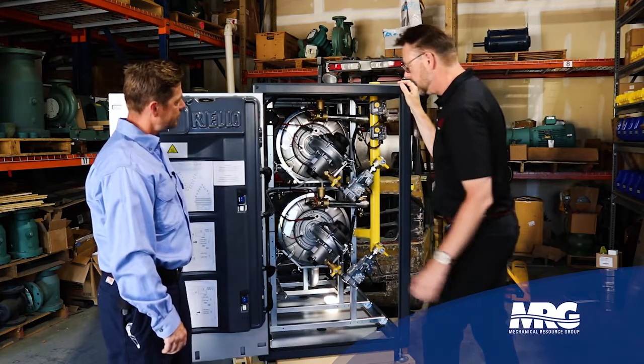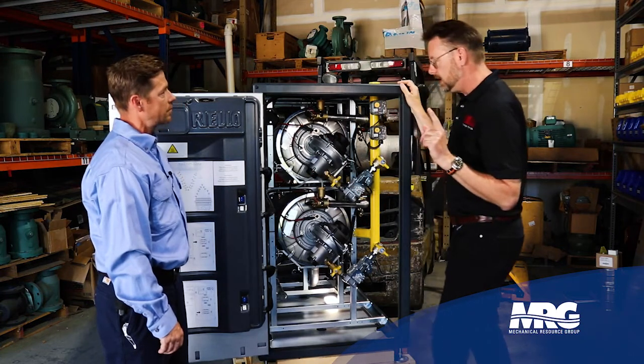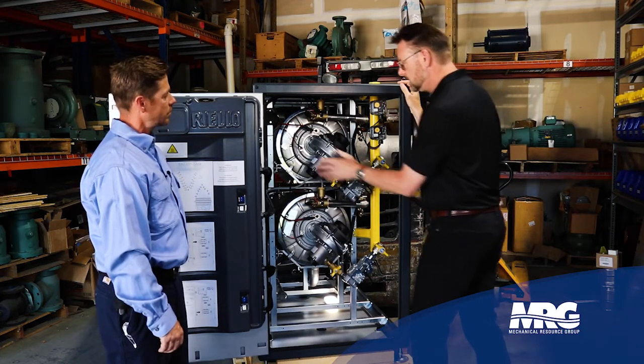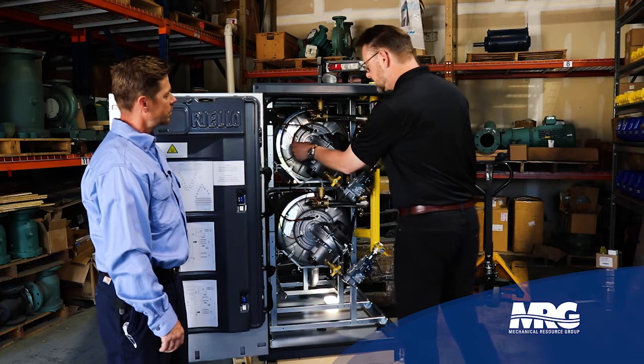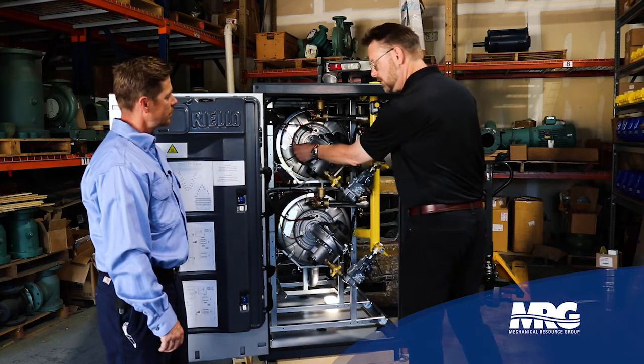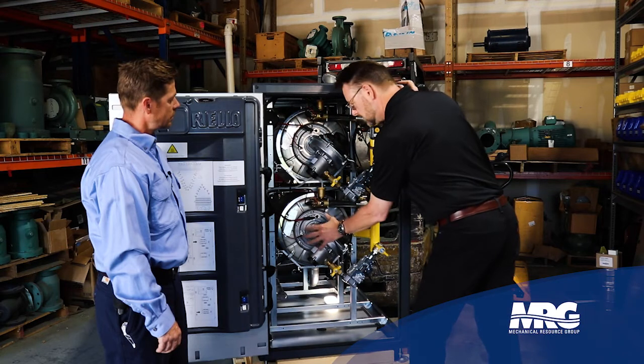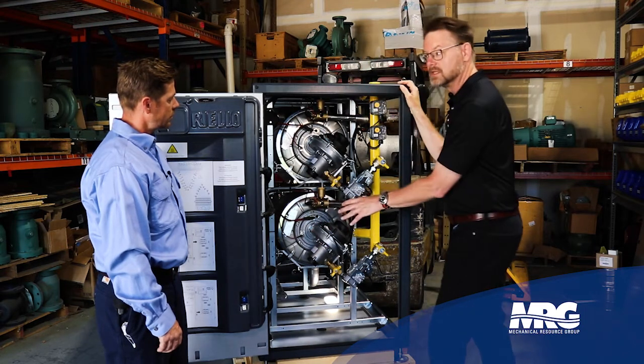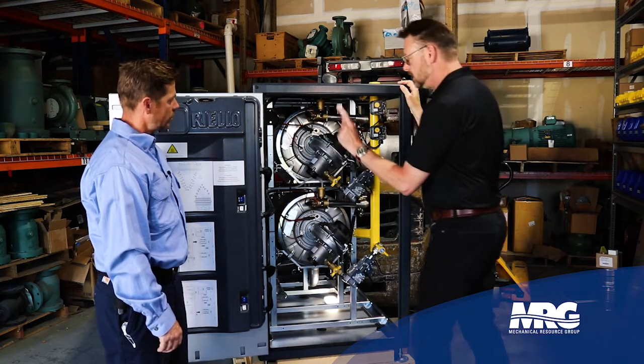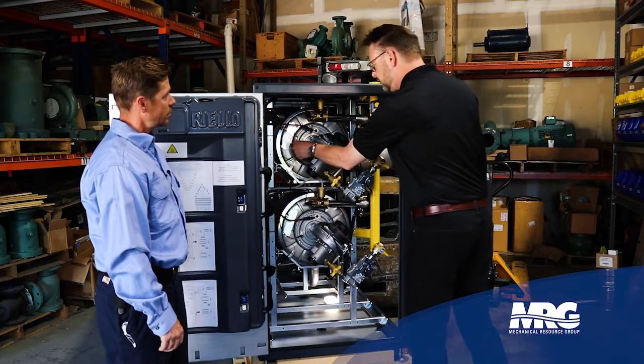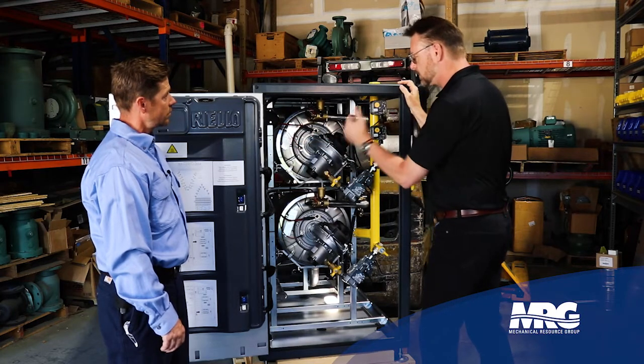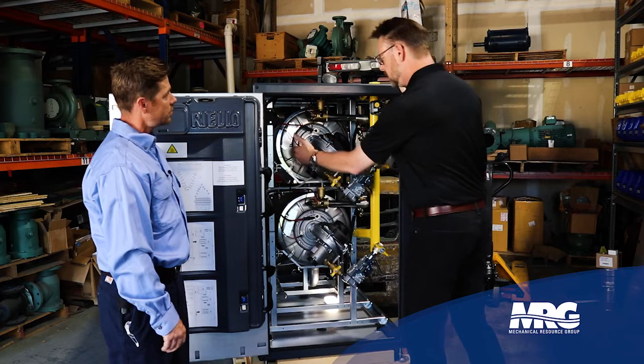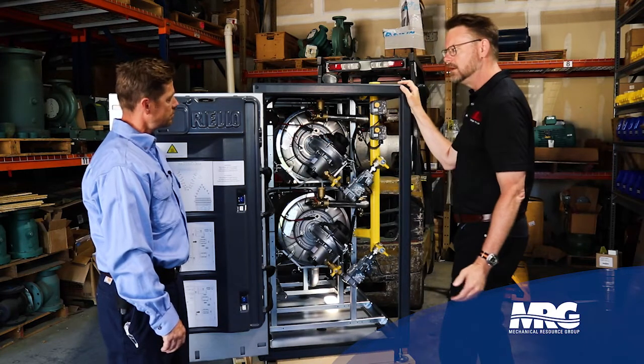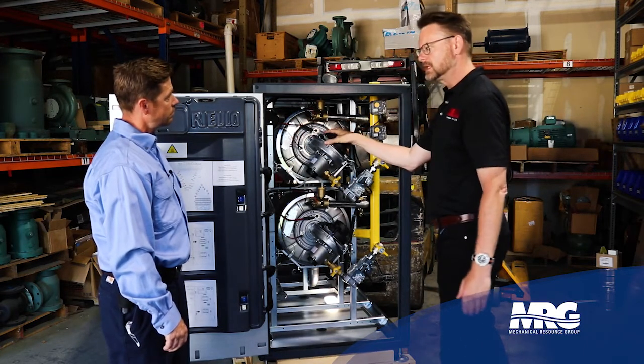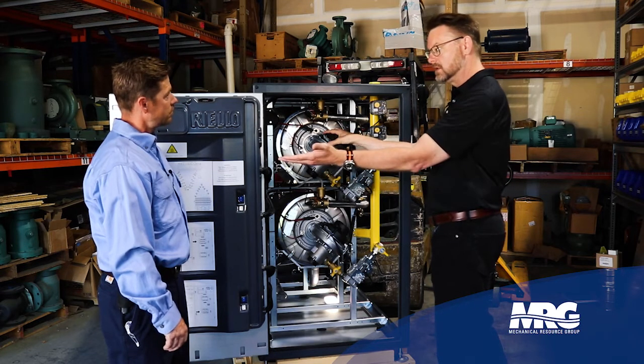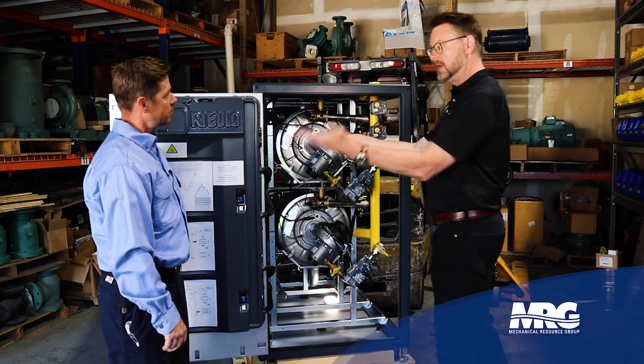Yeah. Okay. In the case of the Riello Array with the multiple heat engines, this Helix has its own ignition system and its own flame proving. So in the case that you went on, Kevin, where you had a failed flame proving system, for example, it would occur here on Helix number 1, and we would lose this heat engine. Like you lost, or you were intermittently losing, that particular boiler.